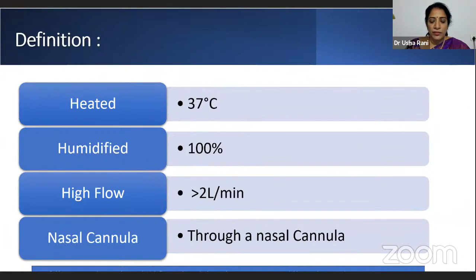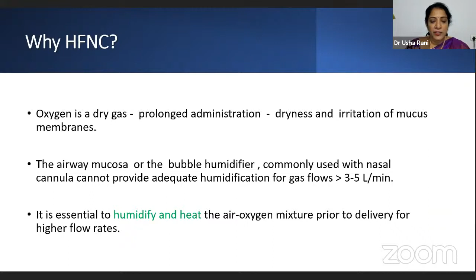And why does HFNC score over conventional oxygen therapy? Oxygen, as we all know, is a dry gas, and if you use it for a long time, it can cause dryness and irritation of the mucous membranes. Dryness, and also cool air, may interfere with the respiratory epithelial ciliary function. The bubble humidifier, which we use along with nasal prongs, will not provide adequate humidification for gas flows of more than 3 to 5 liters per minute. So it is absolutely essential to humidify and heat the air-oxygen mixture whenever we are using supraphysiological flow rates.